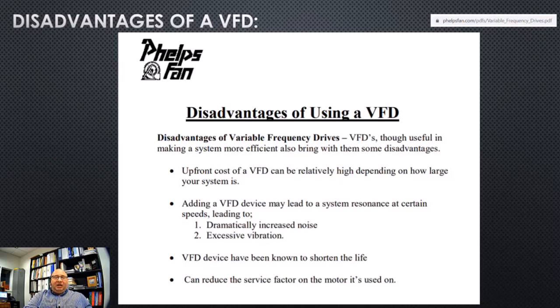All right. It's said that the VFD has been known to shorten the life of the motor. That could be true, but also a false statement. There's some things that you could add to the system to lengthen the life of the motor. Typically, what happens is the motor has been running conventionally all this time. We put a VFD on there, then we might reduce the lifespan of it by converting it from a conventional to a VFD motor. But if you started off with a VFD rated motor from the beginning, there is no real shortening life on it. Actually, it is said to extend the life at that point. And it can reduce the service factor on the motor it's used on.